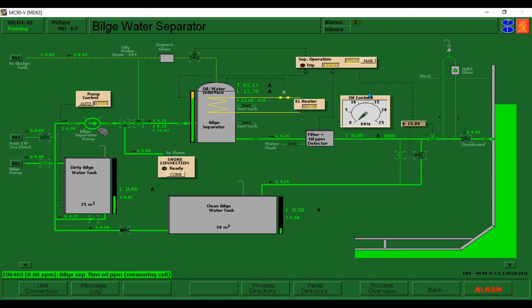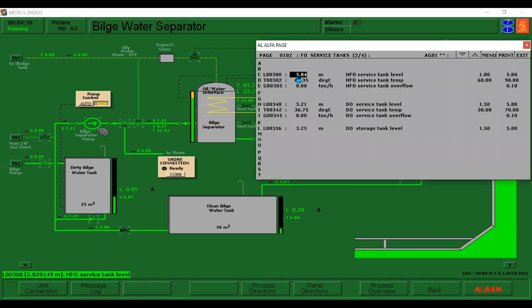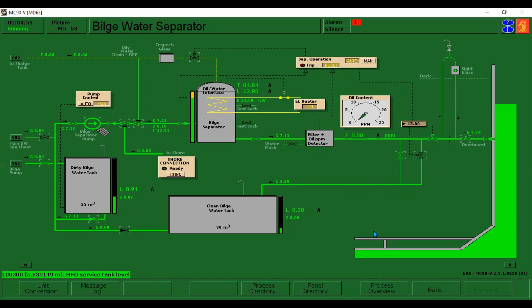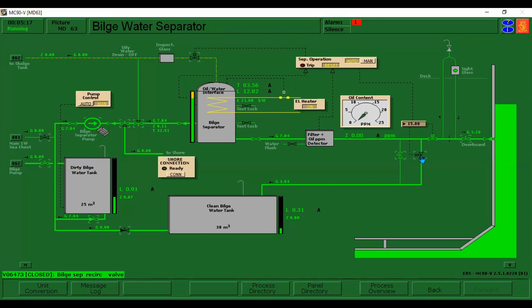The oil content monitoring system is required to operate at only 15 ppm. We are going to set it to 15.0 ppm and enter. Then we open the overboard valve and reset the alarm. You can notice the oil content is now at zero ppm. Once the oil content reaches 15 ppm, the operation of the bilge oil separator continues but the bilge separator circulating valve, or recirculating valve, automatically opens and the water content mixed with oil returns back to the clean bilge water tank.